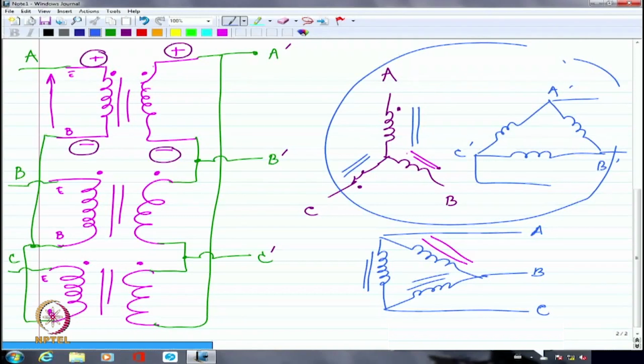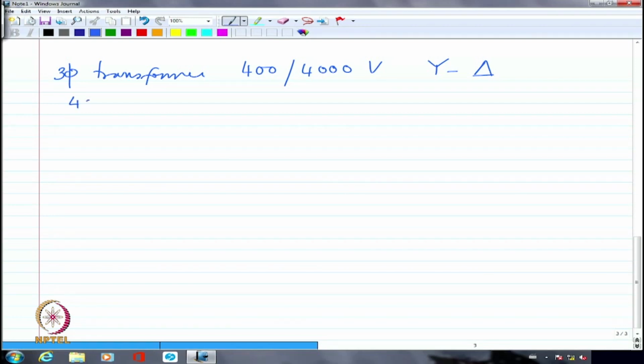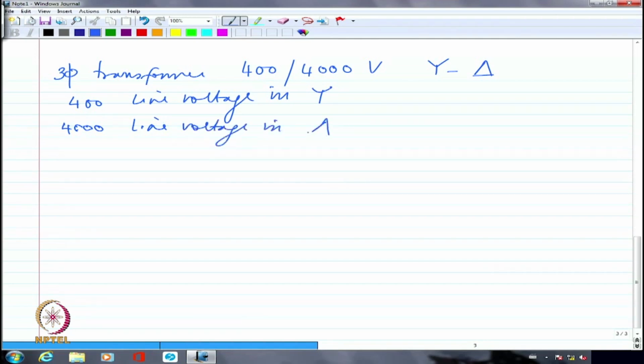Generally, you never take line voltages into consideration for getting the transformation ratio. For example, for a three-phase transformer rated 400 divided by 4000 volts, connected in star delta, 400 is the line voltage in star and 4000 is the line voltage in delta. The phase voltage in star will be 400 divided by root 3, whereas in delta the phase voltage will be 4000 volts itself.